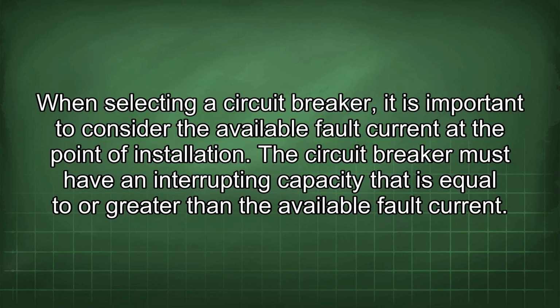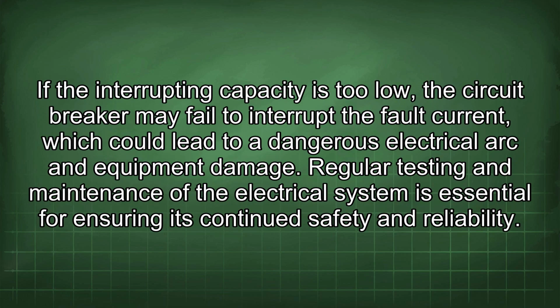When selecting a circuit breaker, it is important to consider the available fault current at the point of installation. The circuit breaker must have an interrupting capacity that is equal to or greater than the available fault current. If the interrupting capacity is too low, the circuit breaker may fail to interrupt the fault current, which could lead to a dangerous electrical arc and equipment damage.